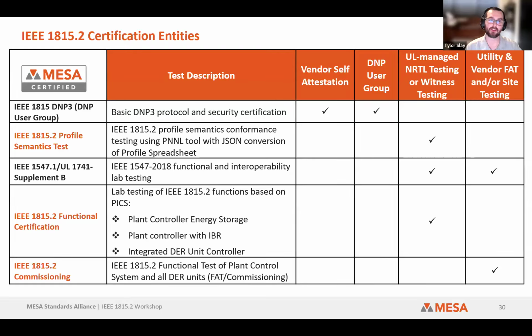No, it is hardware in the loop. UL, I don't know if they have any publications specifically, but they do have hardware in the loop setups. You bring in your device, connect it up to their hardware. They have grid simulators, they have their meters, they have everything. So they can very specifically set up what your device is going to observe and how it's going to respond to those grid events. You can test those mandatory trips, those ride-through settings, your frequency-watt, volt-var functions. All of that can be handled in a very structured manner.